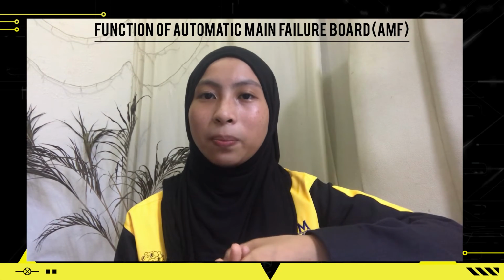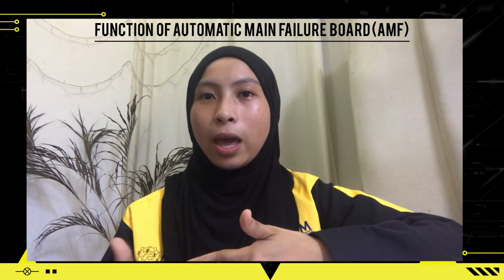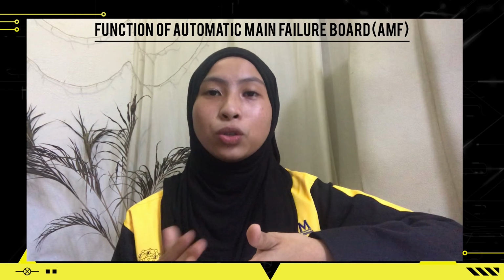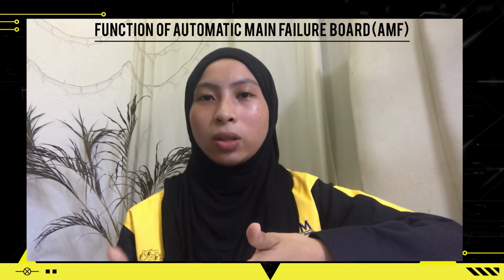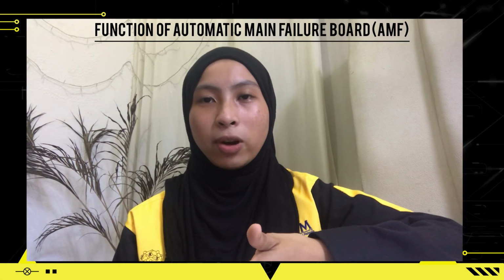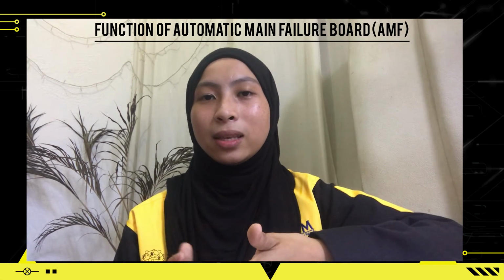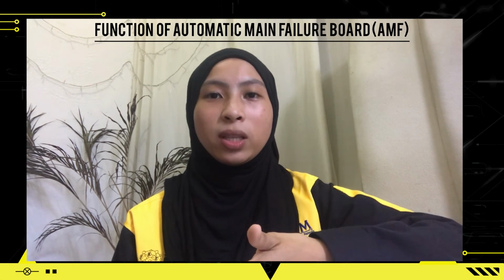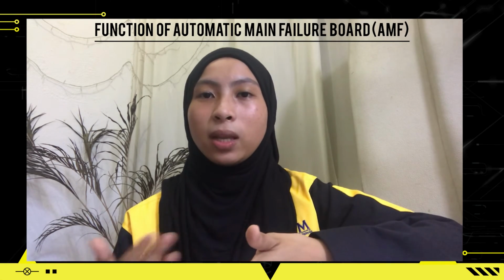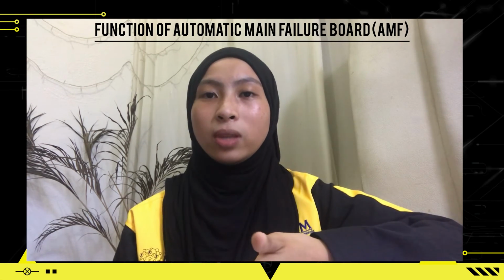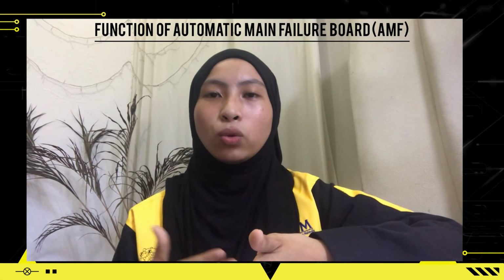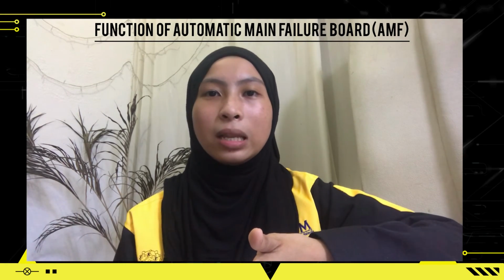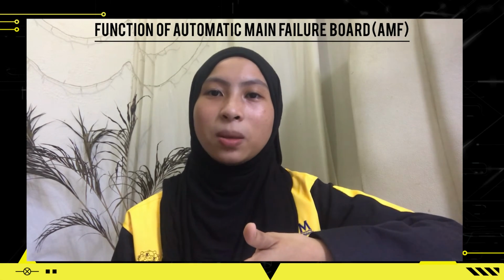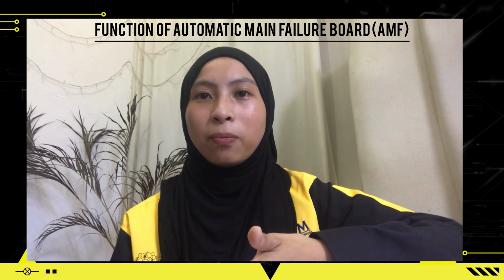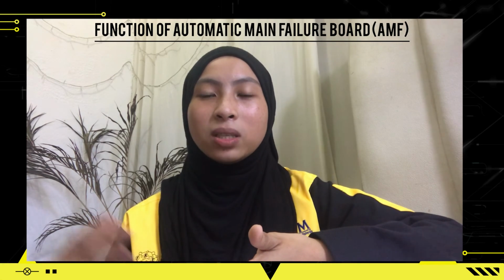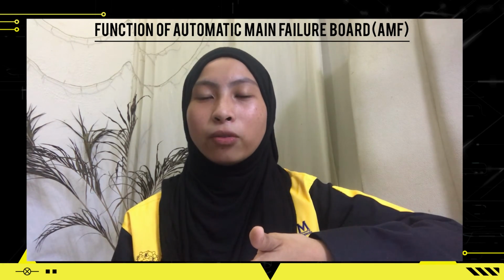When the main supply returns, the AMF panels control a return to the main supply and shut down the generator after a suitable cooling run. AMF panels instantaneously activate the standby generator when main power fails, automatically transfer building loads from the main power supply to the backup generator after about a 15-second warm-up. When the main supply returns, the AMF panels control the return to the main supply and shut down the generator after a suitable cooling run.